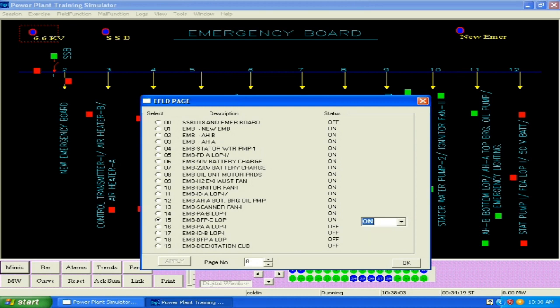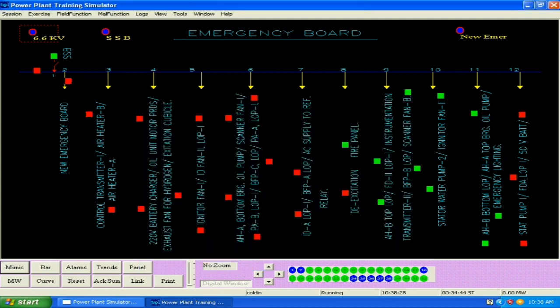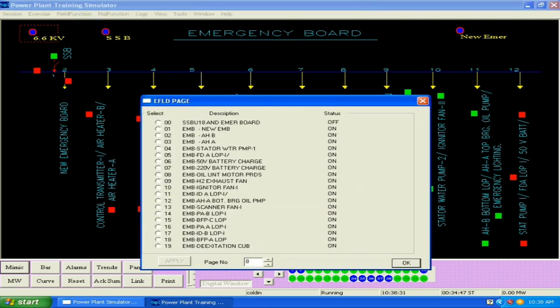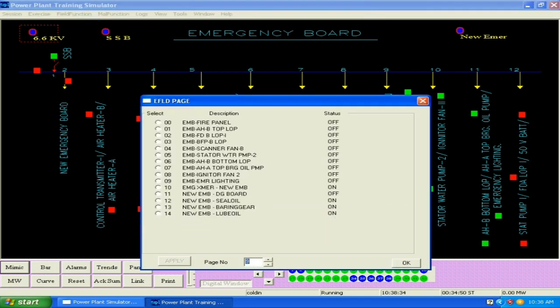So you have to make the supply available to all these emergency auxiliaries. Then there are some emergency auxiliaries on E-field page number 9. So you can go to E-field page number 9, and on E-field page number 9, from index number 00, this is maybe going to firefighting panel, then some air heater, BLOP, like that. So on page number 9, from 00 to 09, all these supplies, emergency lighting also, all these supplies are to be made on.